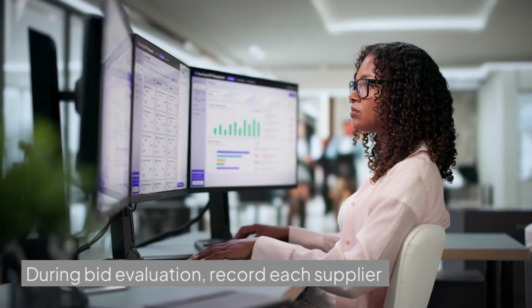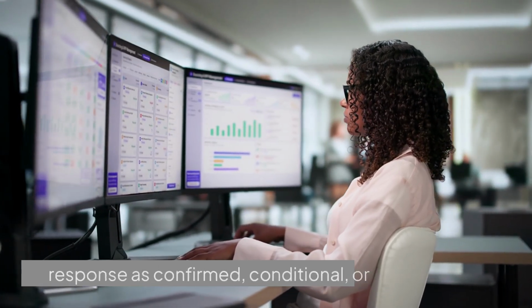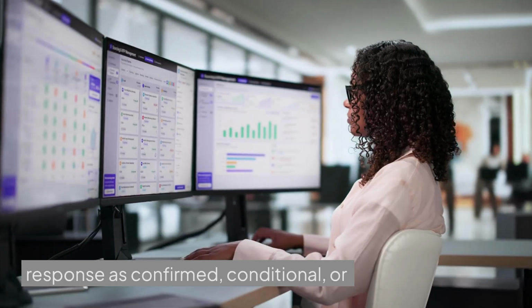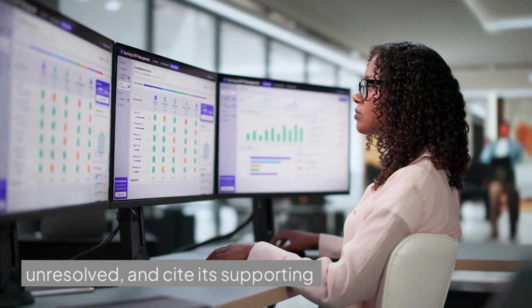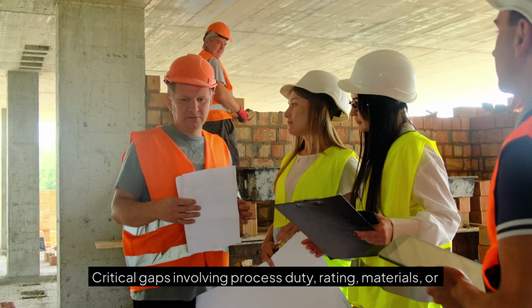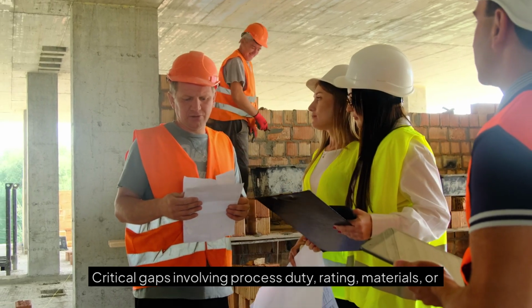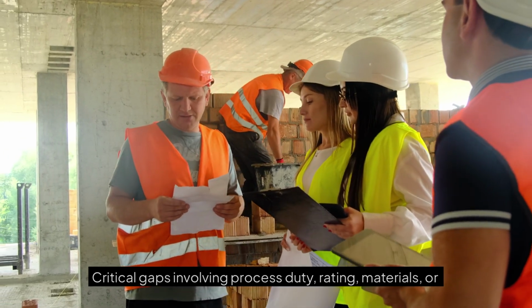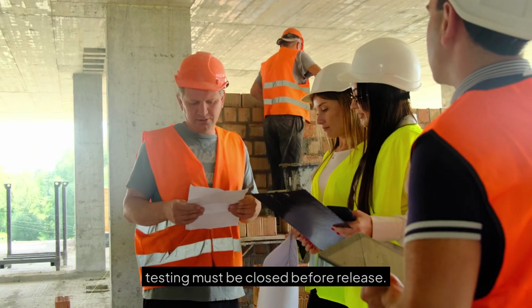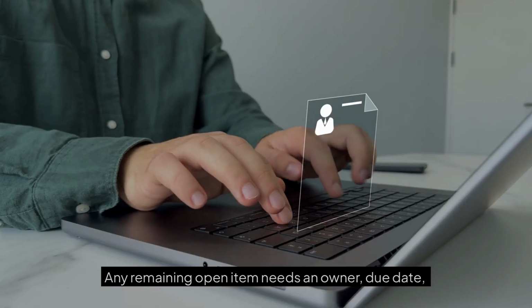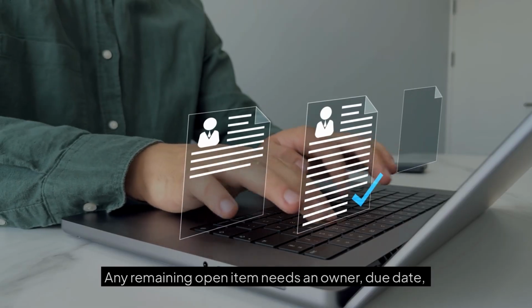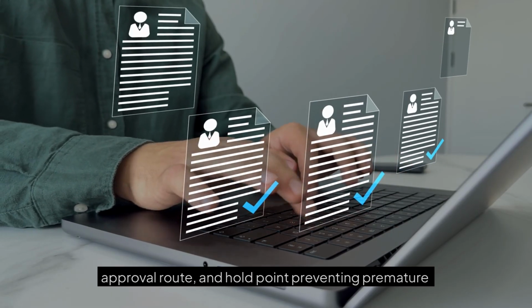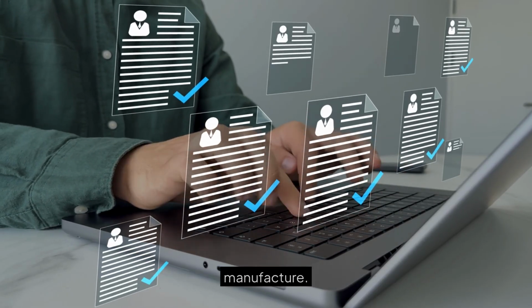During bid evaluation, record each supplier response as confirmed, conditional, or unresolved, and cite its supporting document. Critical gaps involving process duty, rating, materials, or testing must be closed before release. Any remaining open item needs an owner, due date, approval route, and hold point preventing premature manufacture.